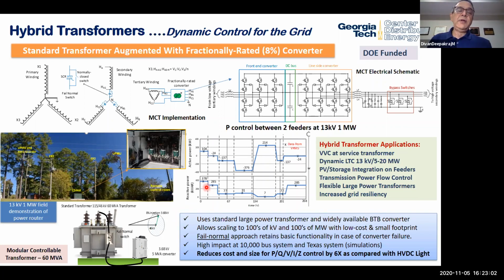This is another example of how you bring control into it. One novel thing we introduced, which is really universal in how we design these things, we call 'fail normal.' We design these so that if the converter fails, it reverts back to a passive device. This was very important for utilities to accept power electronics, because when we started talking to them, they didn't want any power electronics, thinking their reliability was much poorer than traditional power system components. Once we showed them this fail normal capability, they got very comfortable, because it functions like a normal transformer when that device is down.